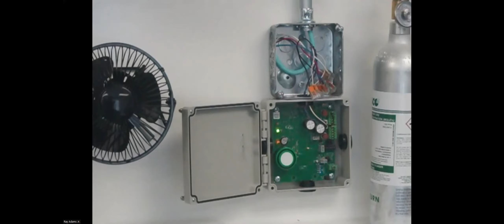Now, generally speaking, from a design standpoint, your building management system might not be in the most ideal location relative to where some of your fans are, or if you're looking at a multi-floor parking garage. And that's where our standalone and control panel come in. The majority of the time, from a design standpoint, the gas detection will be controlling the ventilation. And then in the event that there is a building management system that wants to monitor that, you can have Modbus and BACnet outputs that you can connect into those building management systems.